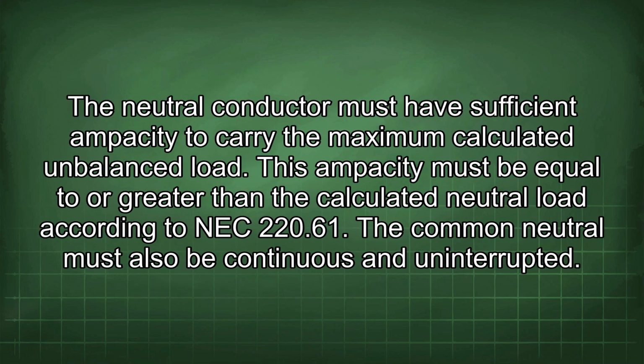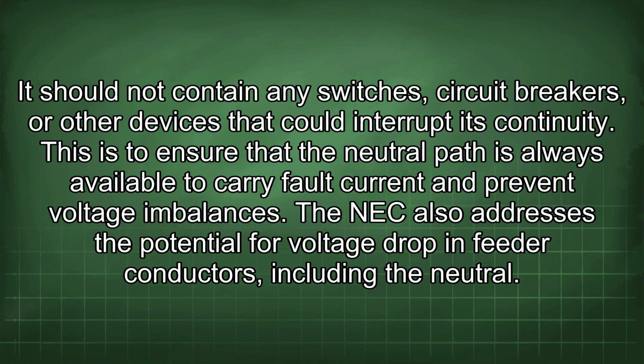The neutral conductor must have sufficient ampacity to carry the maximum calculated unbalanced load. This ampacity must be equal to or greater than the calculated neutral load according to NEC 220.61. The common neutral must also be continuous and uninterrupted. It should not contain any switches, circuit breakers, or other devices that could interrupt its continuity. This is to ensure that the neutral path is always available to carry fault current and prevent voltage imbalances.